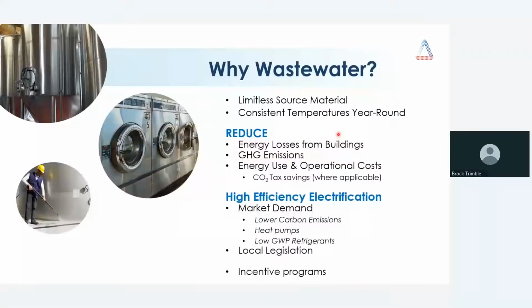So we always get the question, why wastewater? Why is it that we chose to look at wastewater as this source of energy to draw from or to sink to? Well, for one thing, it's essentially a limitless source material. It's always flowing out of our buildings, beneath our feet, throughout our sanitary sewers, and it's that really nice, consistent temperature throughout the year. If you think about all those items that I just discussed, all of your fixtures, you're typically going to use your shower at the same temperature every day throughout the year. You're going to wash your hands roughly the same temperature throughout the year. Because of that, we don't really see too much of a difference when it comes to seasonality or geographic location, and that lends wastewater to be an extremely well utilized source of energy throughout the year.